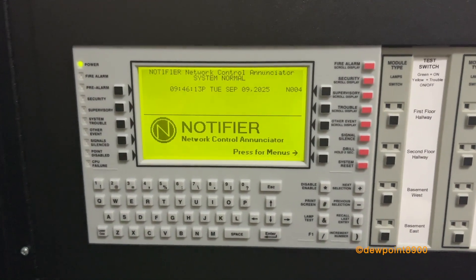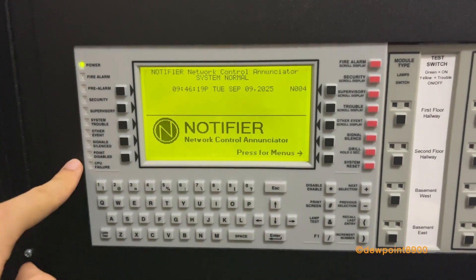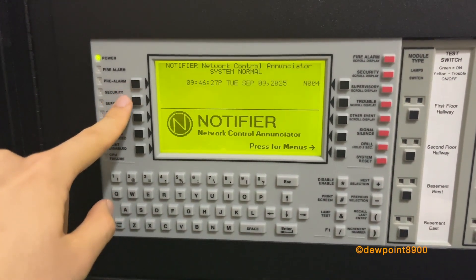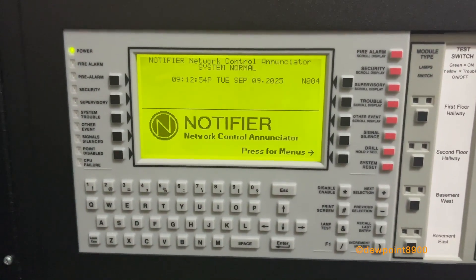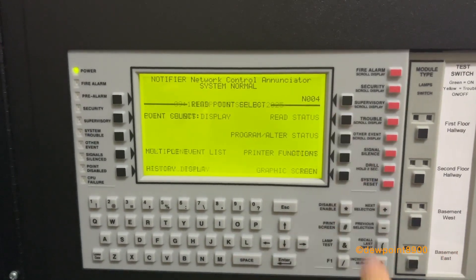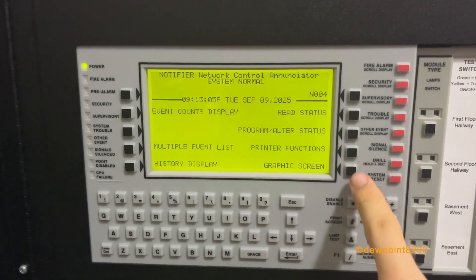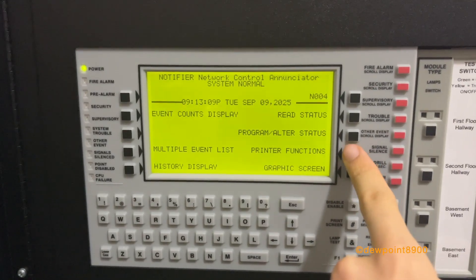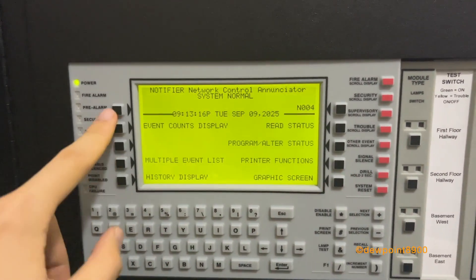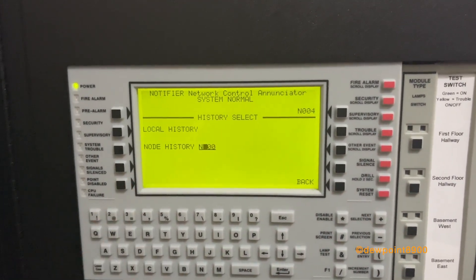The NCA has various buttons and LED indicators to annunciate events on the network. The system indicators are on the left, operator controls on the right, a full keypad like the KDM-2, and additional buttons for prompts on the LCD screen. The NCA is serving as the primary display for this system and also has its own menu interface, including read status. This can be used to view any device on the network, program printer functions, and provides several different views: graphics screen, multi-event list, event counts, and history display.